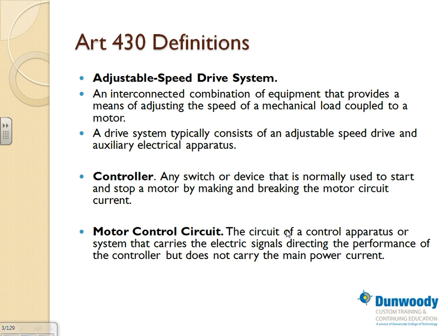The other one is the better one that a lot of us do, and I've done a few of these for wastewater treatment plants, they love it. You can group all the controllers for your motors in one big piece of equipment with an overcurrent protection device and a disconnect in it, and that's called an MCC. If anybody has worked on MCCs, I'm sure a few of you have worked on MCC buckets. You throw the bucket in, and the bucket has a controller and the overcurrent protection device, and you can use it as a disconnect.